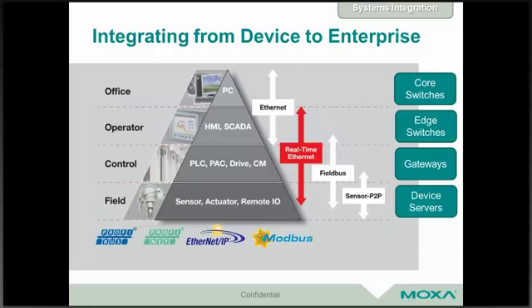When we say field level, we mean basically device servers - serial-based products like sensors, actuators, or remote I/O. You also can integrate control level networks, which we typically refer to as PLCs, PACs, drives, or CNCs. This is the sweet spot for our real-time redundancy Ethernet that we talked about. On the operator level, we refer to devices like HMI and SCADA, and finally on the PC or office level, we're talking pure Ethernet alone.